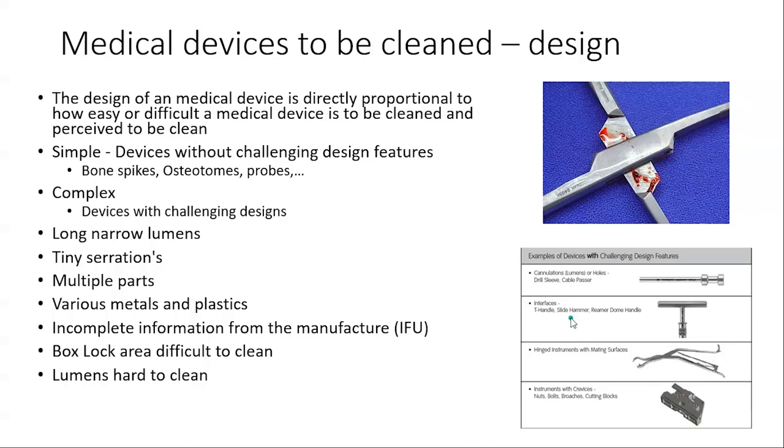Next, we know that the device design — and how it's to be cleaned — has a huge impact. I divide devices into two areas: simple and complex. Simple devices without a lot of challenges include bone spikes, osteotomes, probes, and standard pickups. Complex devices with challenging designs include the box lock — with its nooks and crannies — lumens, multiple parts, and various metals. Sometimes the IFUs are incomplete, which makes it even more of a challenge.